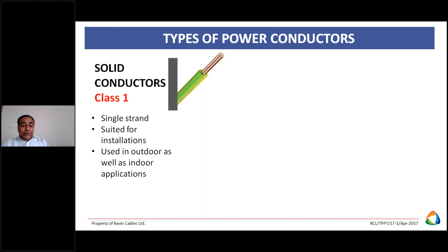Suppose it is extra flexible, then class 6 conductors are there. Normally, the wires we use in our homes, in home appliances, are flexible wires or flexible cords. Suppose you want more flexibility, like welding cables, then class 6 conductors are there. Then what is the difference? In class 1 conductor, only one wire is there, that is a solid conductor. In class 2, it is the stranded conductor, which requires a minimum number of wires as per the required national or international standards. Then in class 5 or 6, the maximum diameter is fixed.